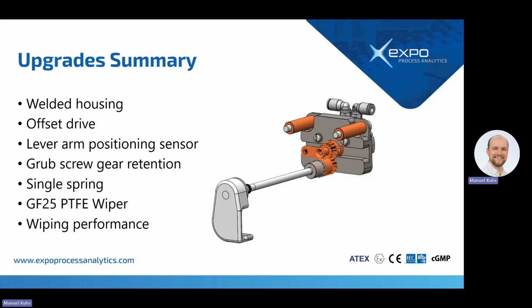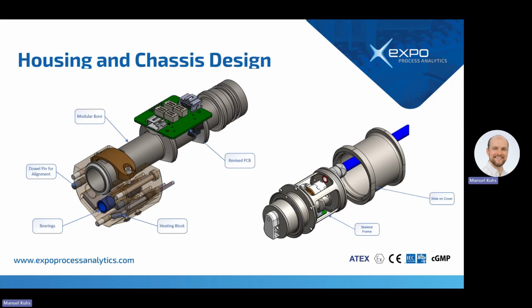Breaking it down: the revised housing and chassis design. The probe bore is now modularized so it can be changed depending on the probe configuration being used. Our default is a 3/4 shaft probe, but you could integrate sapphire windows into the front for non-contact applications, or make the bore smaller for a smaller diameter probe.